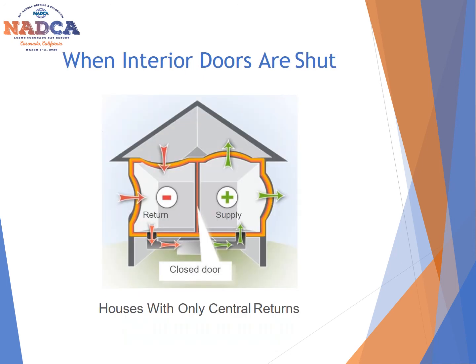Let's take a look at this picture here. In this particular case, you have 2 rooms, and the system is designed for the door to be open so air can easily pass from one room to the other. If you were to close that door, on one side of the system you have a positive pressure, and on the other side, because it's not getting the makeup air it needs, you now have a negative pressure in the room on the left. That air has to come from somewhere, so it's going to start going through cracks in the windows.